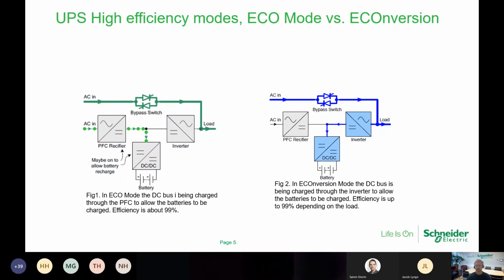First, I want to explain a little about two types of high efficiency modes, called Eco mode, figure 1, and ECOnversion, figure 2. High efficiency mode is a UPS operation mode for which the primary goal is to reduce system power loss and increase efficiency compared to inverter operation, normal operation, or battery operation. Higher efficiency and smaller loss make the UPS more green. In normal operation, efficiency is from 93 to 96%, depending on the load, but in high efficiency mode it's about 99%, in Eco mode up to 99% in ECOnversion, depending on the load.